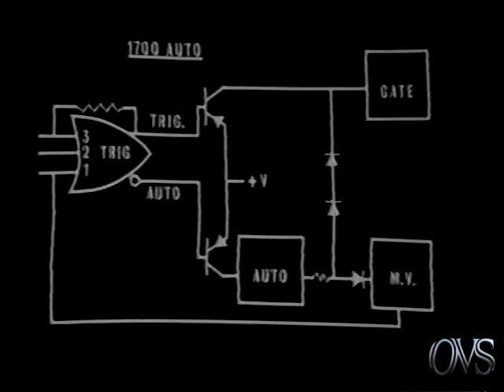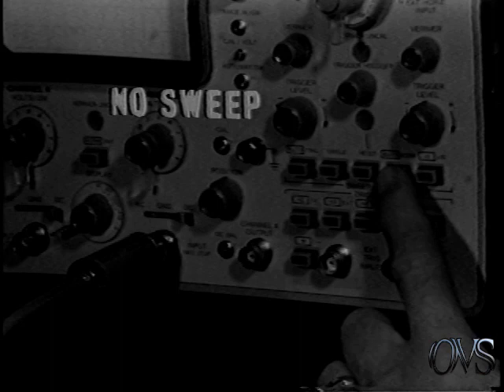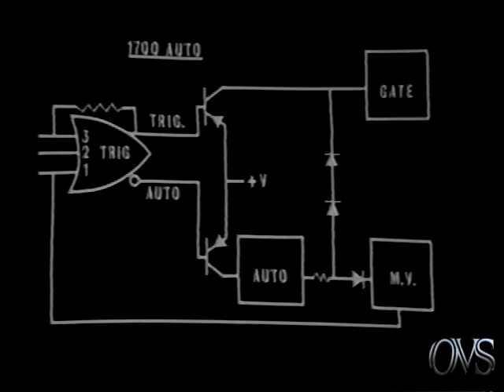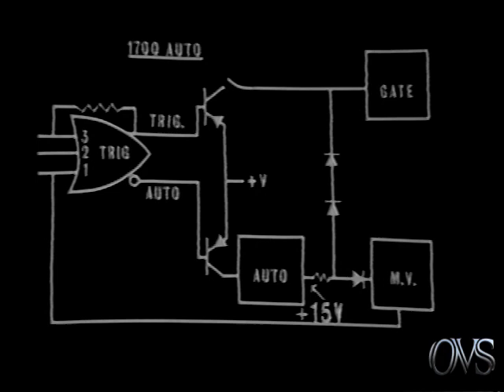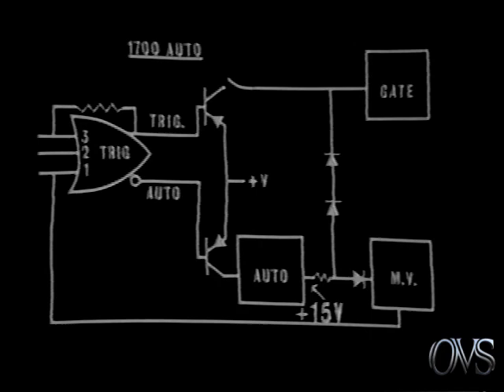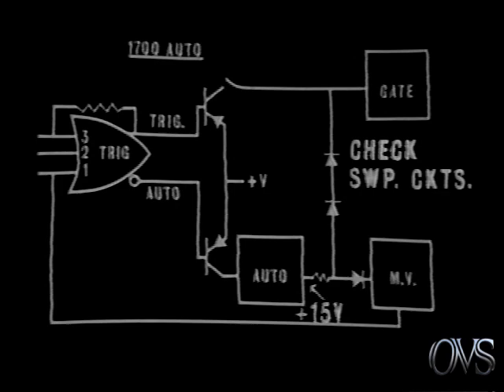The auto-sweep mode can be helpful in isolating time-based troubles. With a vertical input signal connected and no sweep in either normal or auto mode, select the auto mode. Then, lift this collector lead. This transistor is now turned on regardless of the input. Under these conditions, a properly operating auto circuit will supply plus 15 volts at this point. With plus 15 volts here and still no display, check for troubles in the sweep circuits: the gate, integrator, comparator, and monostable vibrator.